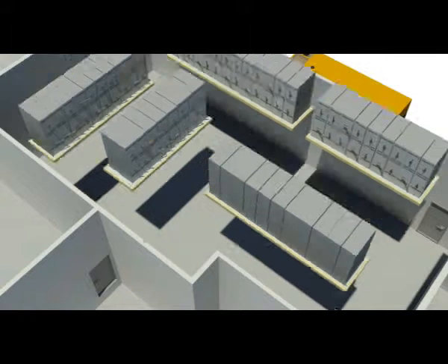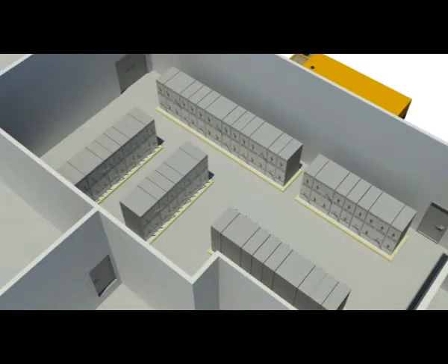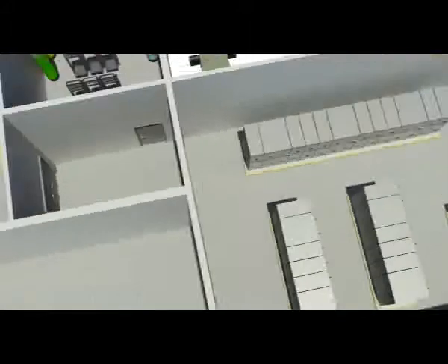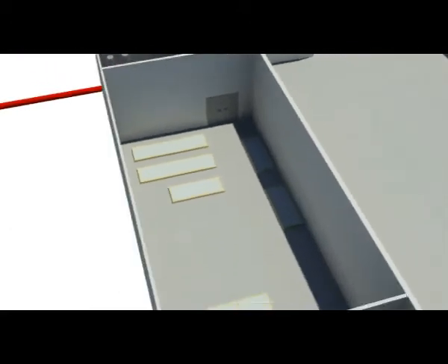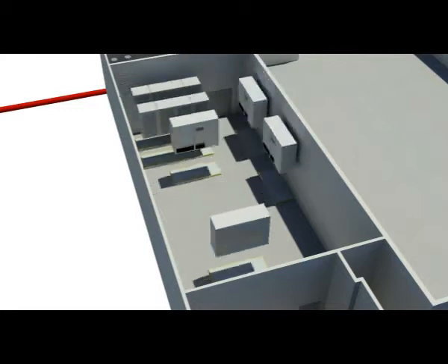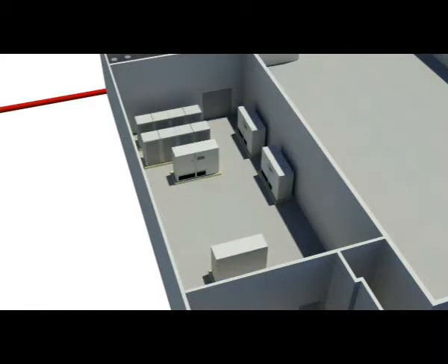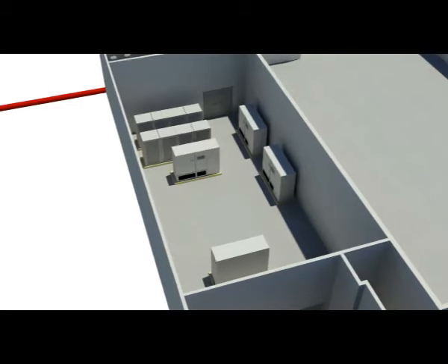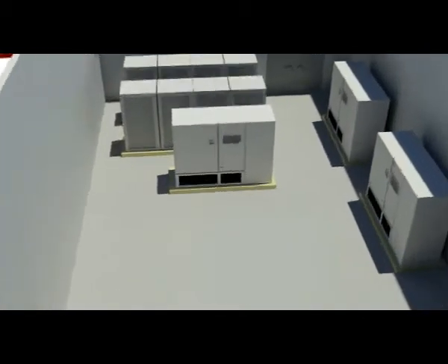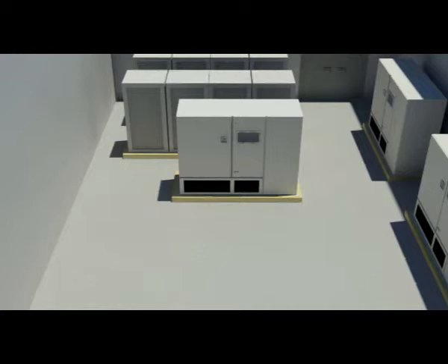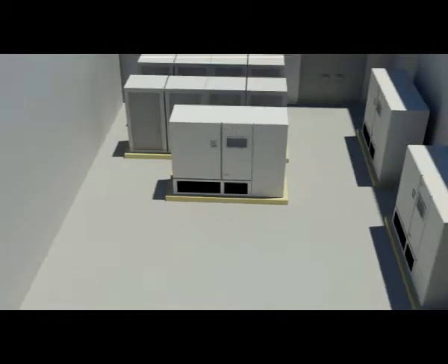All power sources transfer through redundant electrical switchgear, a system that manages a smooth transition of power between supplies as needed. Both the A and B power feeds are constantly fed into uninterrupted power supply systems that can power the entire data center as power is being transferred from commercial power to generator. These layers of redundancy are how we ensure that power to the customer equipment is never absent, regardless of any emergency or unexpected power failure outside the facility.